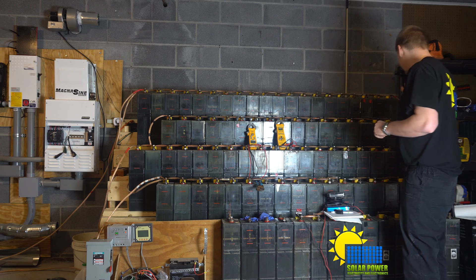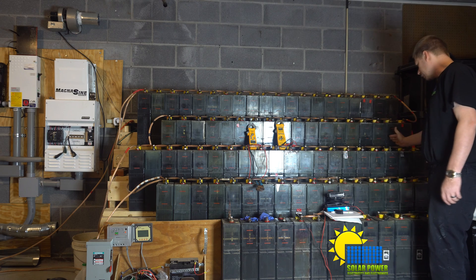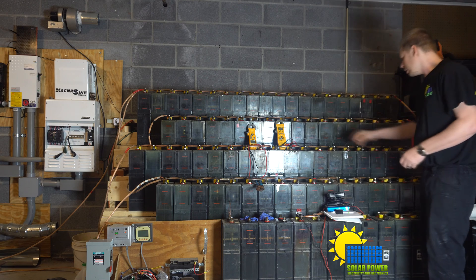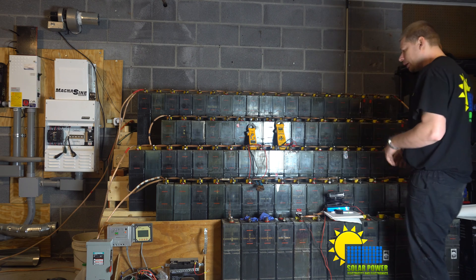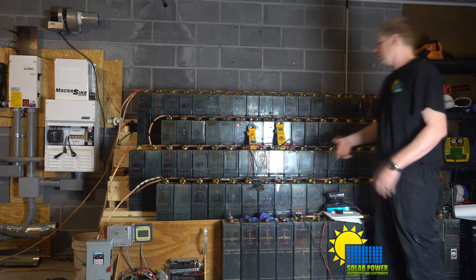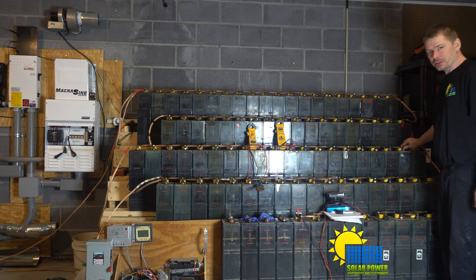These two batteries are ready to go. It's important that I've marked all of these — you can see the black tape on this cap. I use black tape for a battery that's ready to be changed, a red marker means it's a happy battery, and black on the terminal means it's the next battery that needs to come out because it's reversing polarity. I've got two reversing polarity right now.